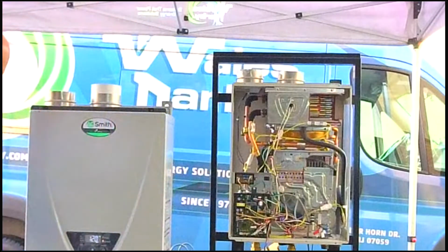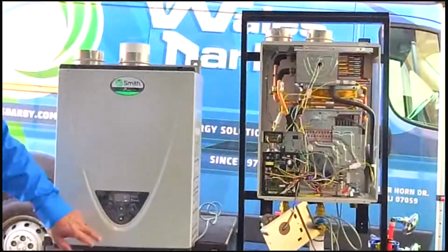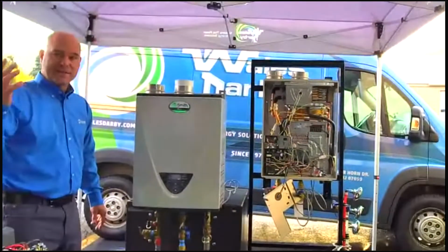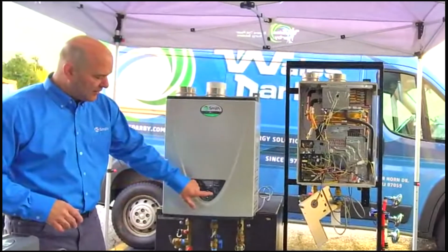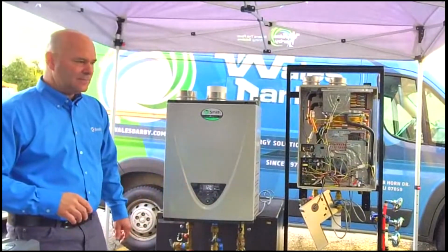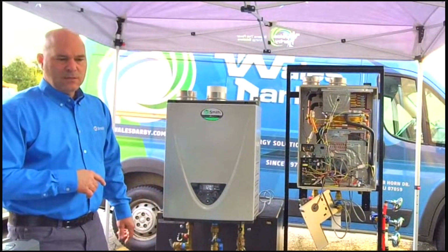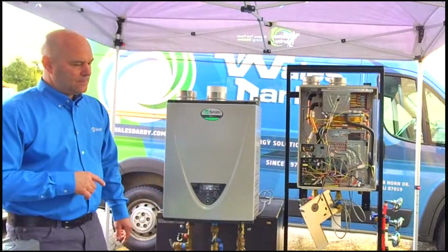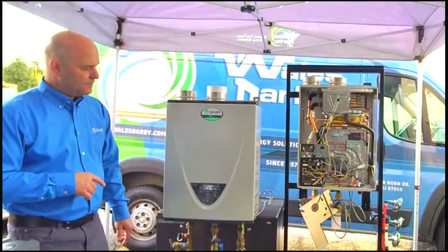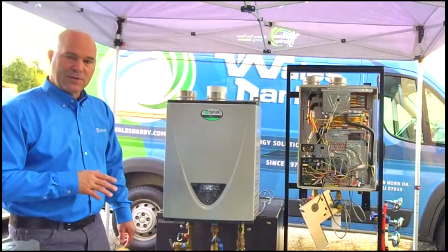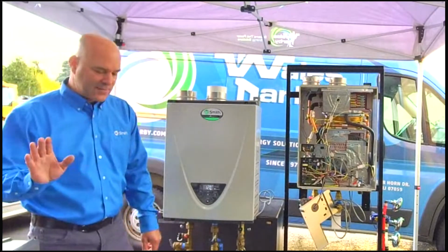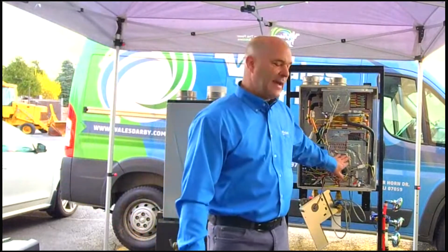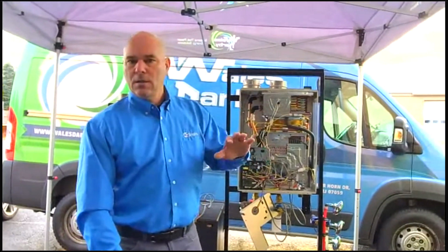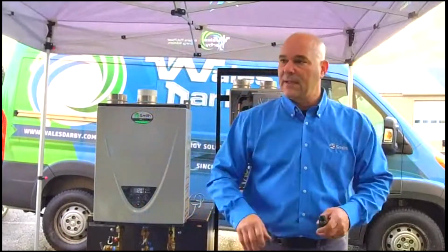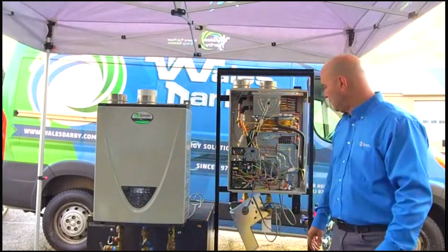On the gas valve side, I am going to just shut this unit down, and hopefully we're outside, so hopefully you'll be able to hear this. Every time you turn the unit on, I'm not sure if you heard the gas valves. Can't hear the gas valves? Okay. You'll hear the gas valves. The solenoids will clunk. So I just wanted to try to show you, but again, we're outside, so it's too loud out here to hear it.